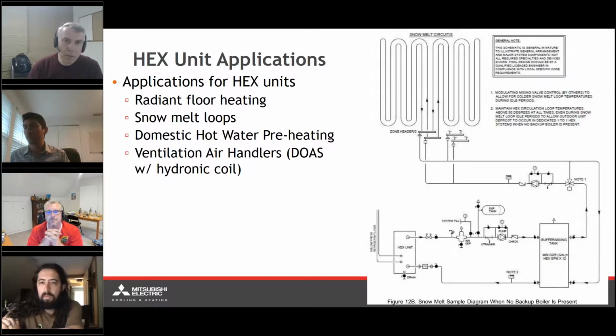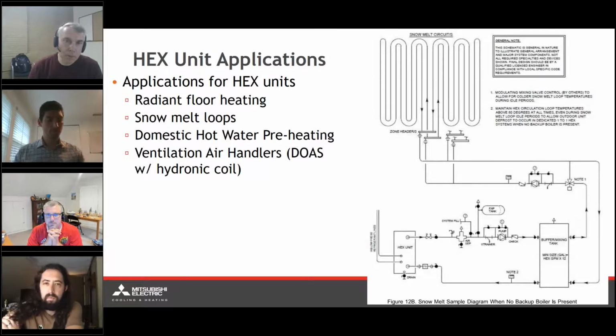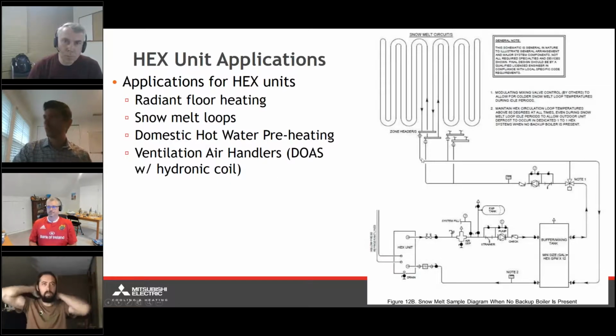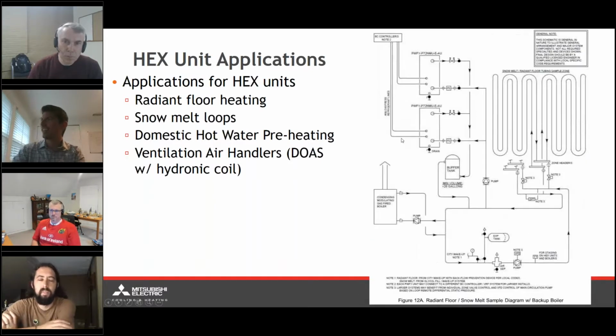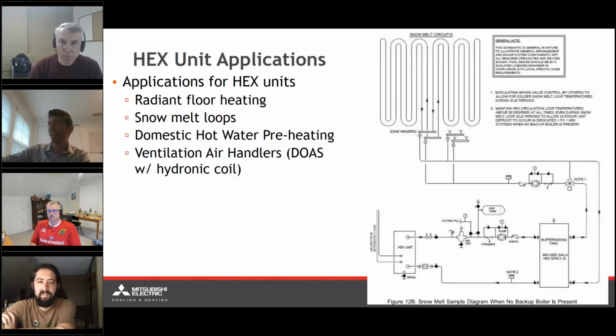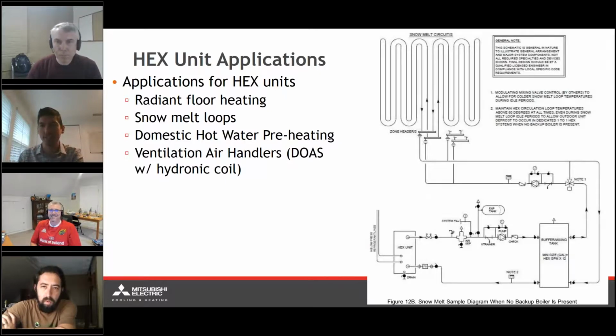Correct me if I'm wrong, Mike, but I think the HEX is allowing an outdoor unit to take over the function of a boiler. Yes, that is correct. Forgive me, this last slide is how we would do the snow melt radiant floor tube with the boiler. This slide, I don't even know why I have the previous one in there. This is done where it eliminates the gas-fired boiler. So this one is entirely done with a HEX unit with no backup boiler present.